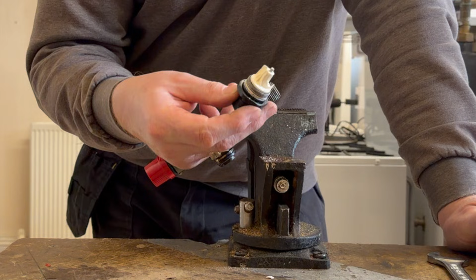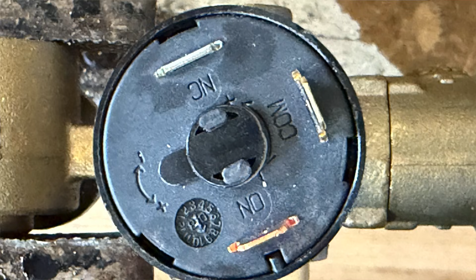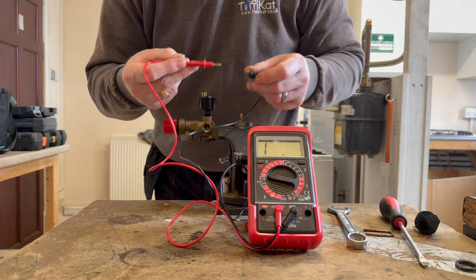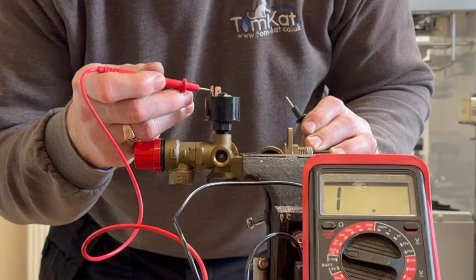Next we can look at the low water pressure sensor. There's three connections on here - a common, a normally open, and a normally closed. They only use the common and normally open on this one; the normally closed isn't there, but we can still test it. I've got my multimeter set up on the buzzer. I'll go onto common, and if I go to normally open there should be no buzz - which there isn't. If I go to normally closed there should be a buzz. So that's telling me the low water pressure sensor's working.